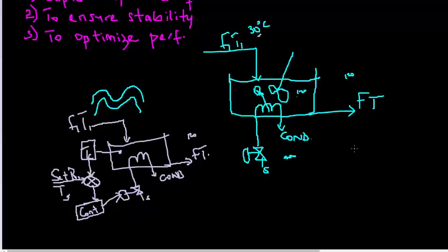The controller would have determined that, okay, this thing is not up to the set point. It tells the valve that we need more steam. Now the valve will increase the steam. The valve will open more, more steam will be passed here to increase the temperature. This process will continue until you get your final temperature. Now you can see the essence of a controller.